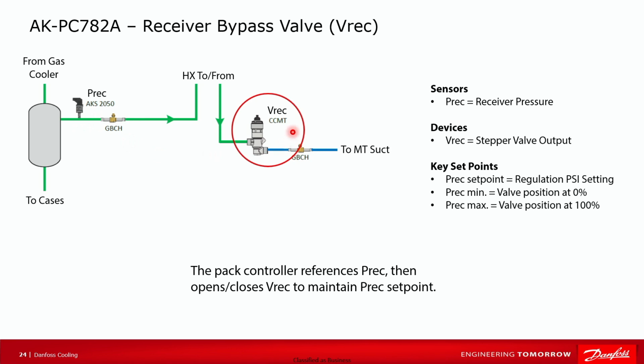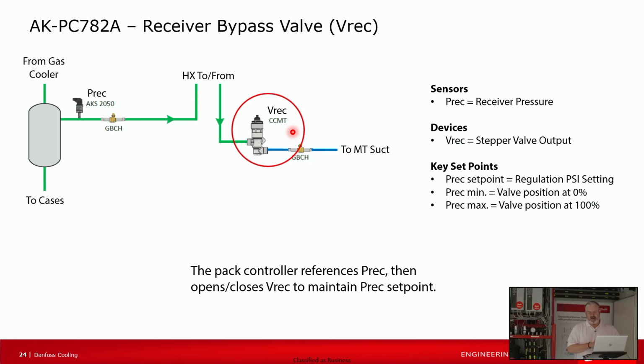Troubleshooting wise, these are the two new parts of the system, the high pressure valve and the receiver bypass valve. And typically they're not the issue. Most people would think they are because they're not familiar with them, so that must be the problem. But for the high pressure valve, if it's a warm ambient and it's towards an open position, it's working. If it's a cold ambient and it's towards a closed position, it's working. The receiver valve, if it's maintaining flash tank pressure plus or minus 5 to 10 pounds, is doing what it's supposed to.